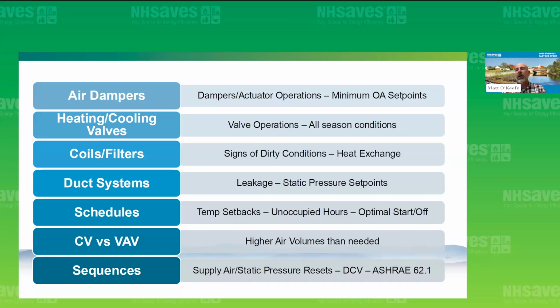could be substantially less now. And then we still are finding a ton of places where, when COVID conditions happened, everybody said run outside air 100%, or a lot more than what was needed. And so those still haven't all been found and corrected and put back to regular conditions. And now ASHRAE allows using indoor air quality as a way to compare your minimum ventilation requirements, which allows for a much lower amount of outside air being introduced into an air handling system than what would have otherwise been required just a few years ago.